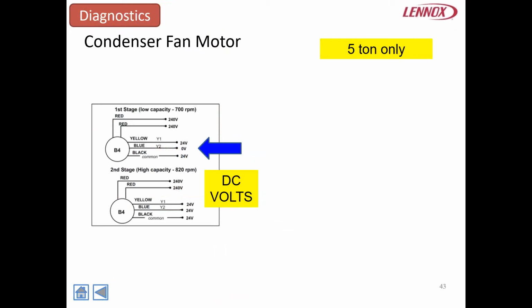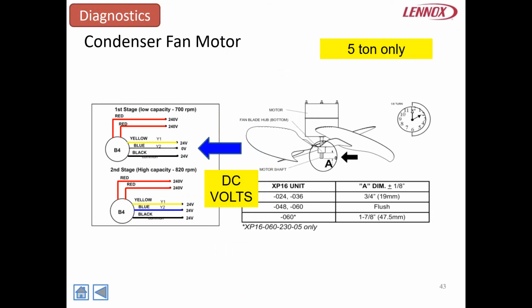So this is 700 RPM on low and 820 on high. We're always going to have line voltage, and then we add Y1 and Y2 on our 24 volts DC to trigger and tell the motor what stage we need to be running in. So we have Y1, and if we want a Y2 input, we just add the extra line along with the first line, Y1, and that says we're in high stage.